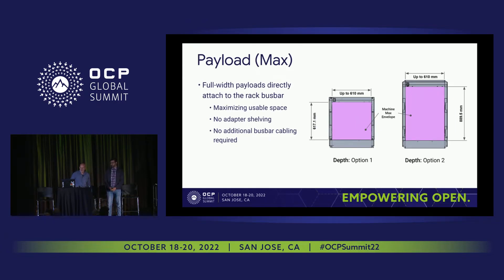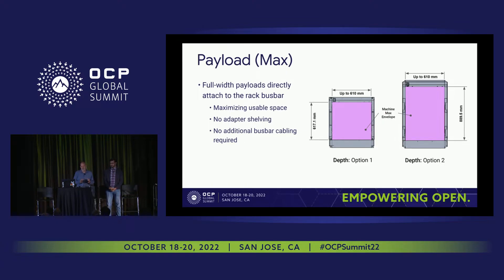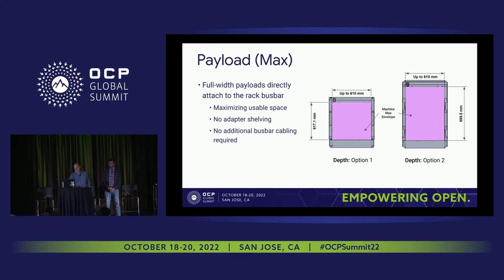In the rack, if we wanted to do what I would call a maximum dimension payload, we're using the entire 610 millimeter width of our internal dimensions of the rack. For deployments where you want to maximize number of servers, there's overhead in the rack — sheet metal and power — which is divided by your number of servers. When you want to maximize your number of equipment inside, you would do a maximum width and direct connect to the bus bar. That would be achieved with floating connectors on your payloads, direct connect to the bus bar, full width — so there's no adapter shelving or anything required.